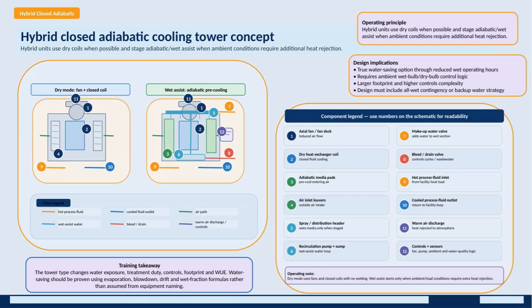This slide presents the hybrid closed adiabatic cooling tower concept, which is especially valuable for data centers with specific cooling and water efficiency needs. The key idea here is that hybrid units primarily use dry coils to reject heat when conditions allow. This means the system operates in dry mode with fans and closed coils, which significantly reduces water use. However, when ambient temperatures and loads increase beyond a point where dry cooling alone is sufficient, the system shifts to a wet assist mode. In this mode, adiabatic pre-cooling sprays water on media pads to cool the incoming air, enabling increased heat rejection. This staged approach ensures water is only used when absolutely necessary, making it a true water-saving option by reducing wet operating hours.